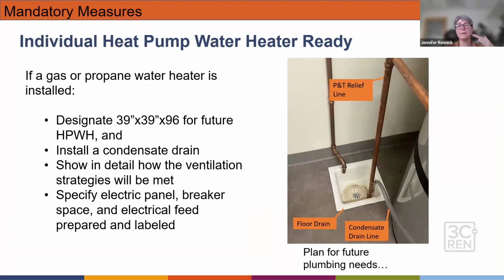And then kind of back to the individual dwelling unit level. If you do individual dwelling unit gas water heaters, then part of the electric ready requirement is to designate a 39-inch by 39-inch by 96-inch tall future heat pump water heater space, and you need to install the condensate drain. So you can install a gas unit, but you need to have that drain ready to go and be there for when it is needed, in addition to the electrical requirements for the future installation of a heat pump water heater.